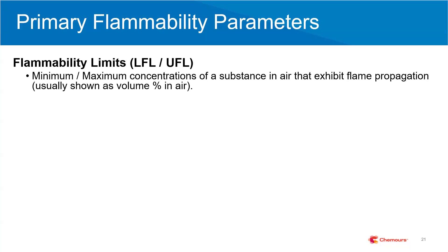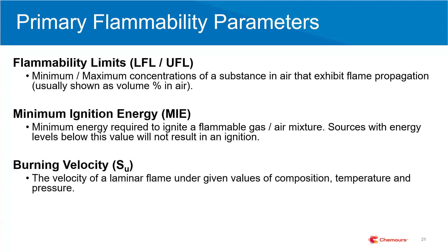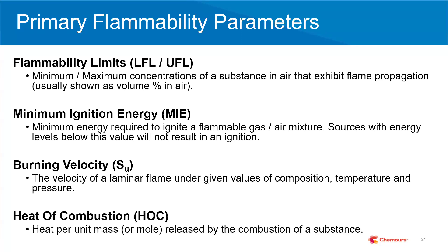If you're below the LFL, you don't have enough fuel for ignition. If you're above the UFL, you're too rich in fuel and don't have enough air. To have a flammable concentration present, you need to be between the LFL and UFL. If you do have a flammable concentration, you need to be concerned about sources of ignition — and that's where minimum ignition energy, or MIE, comes into play. MIE is the minimum amount of electrical energy required to ignite a flammable refrigerant in air. If your electrical energy sources are below the MIE levels, they're not a source of ignition.